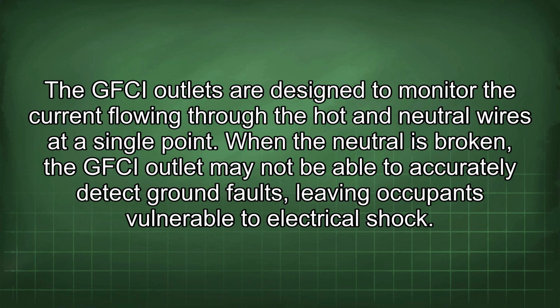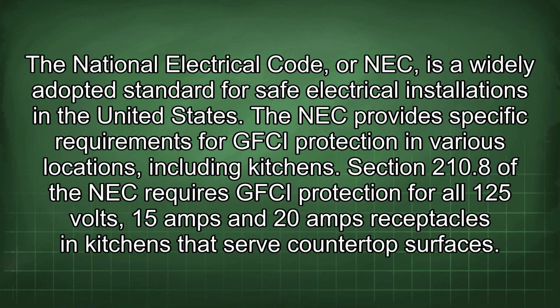The National Electrical Code, or NEC, is a widely adopted standard for safe electrical installations in the United States. The NEC provides specific requirements for GFCI protection in various locations, including kitchens. Section 210.8 of the NEC requires GFCI protection for all 125 volts, 15 amps and 20 amps receptacles in kitchens that serve countertop surfaces.